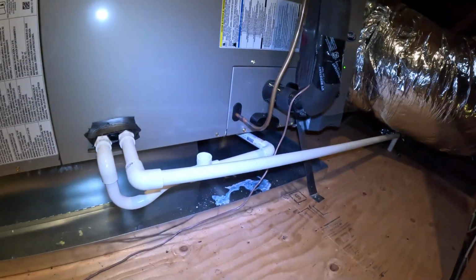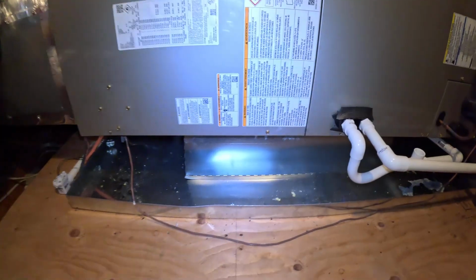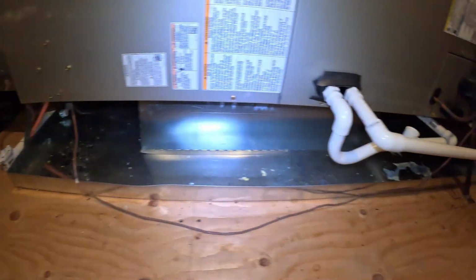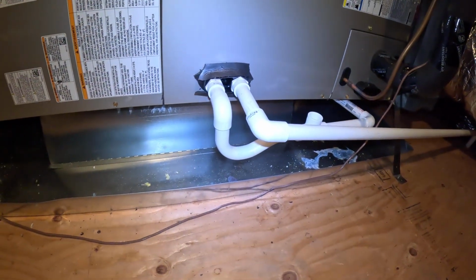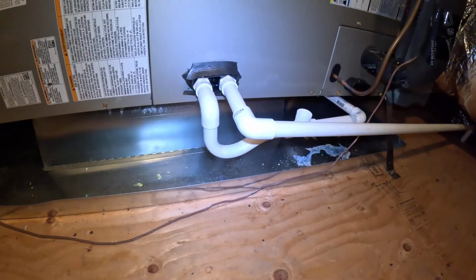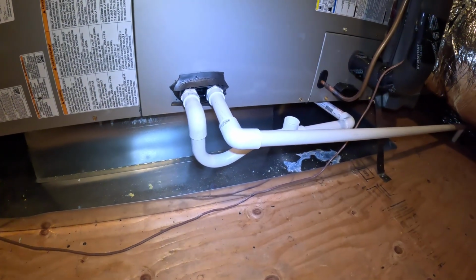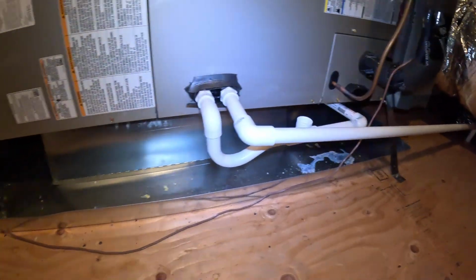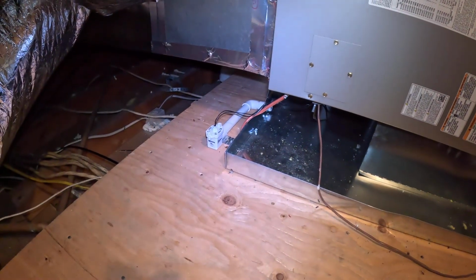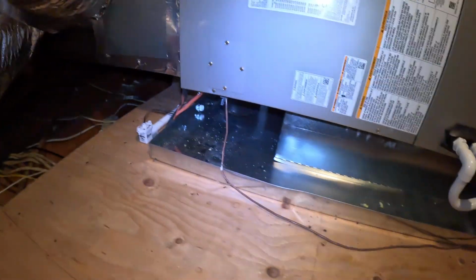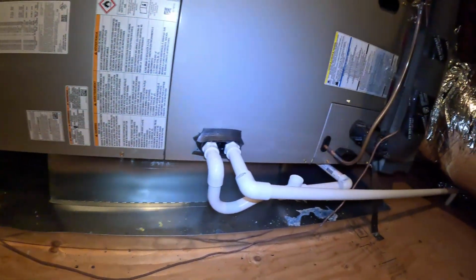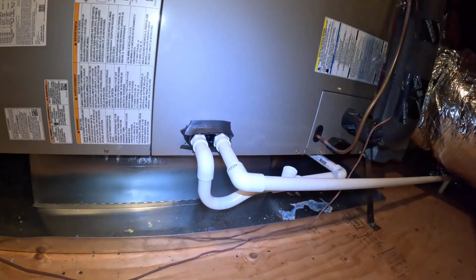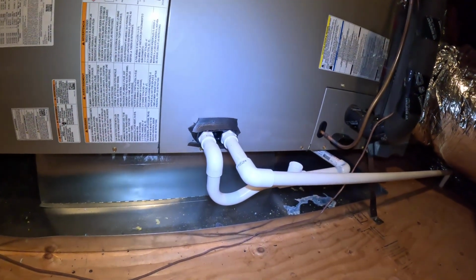Other things up here: it's horizontal, on stands, and we have a drain pan underneath. We have a primary drain that goes outside into a drain, and a secondary that goes over a window. Then we have the pan, so if any water goes into that pan, we have a kill switch on the end here that will kill the system. So we have 3 fail safes, meaning no water would ever get through the ceiling and damage anything.